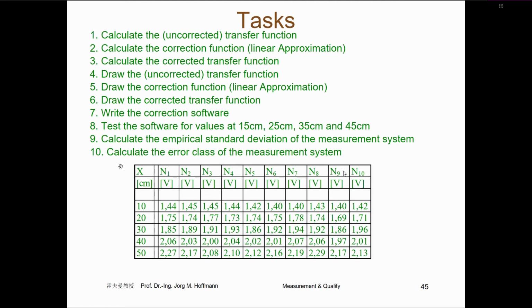You have the calculation of the systematic error, the correction of the systematic error. You have to write the correction software. You can test the software also with values between the calibration points. And in the end, you should calculate the empirical standard deviation. That means the scientific method of the expression of the random error, and you should calculate the error class. That means that you calculate the expression of the random error with a non-scientific, often practically used method.